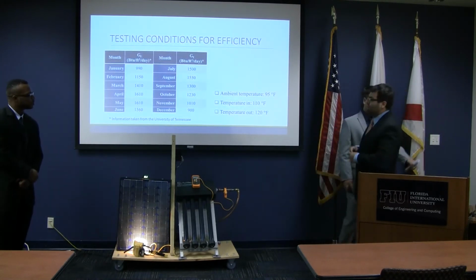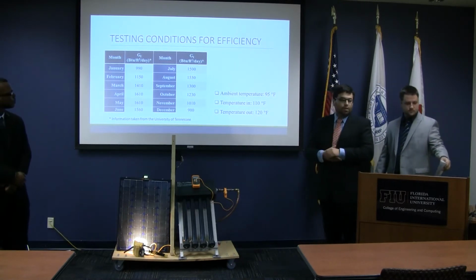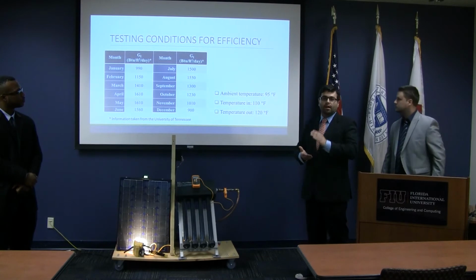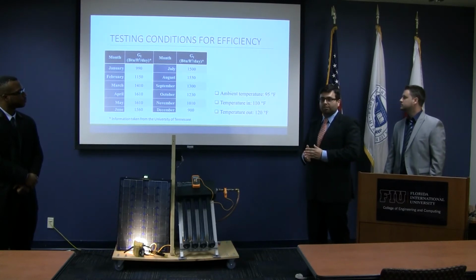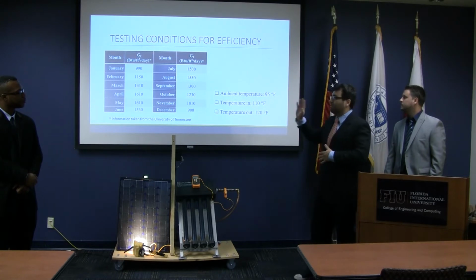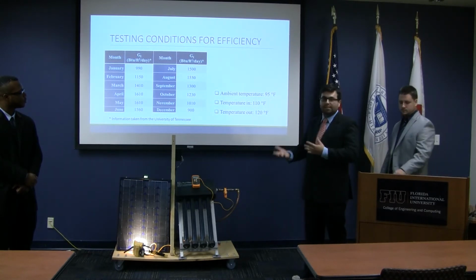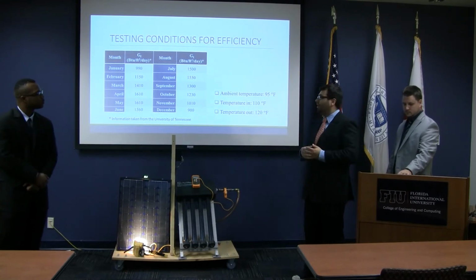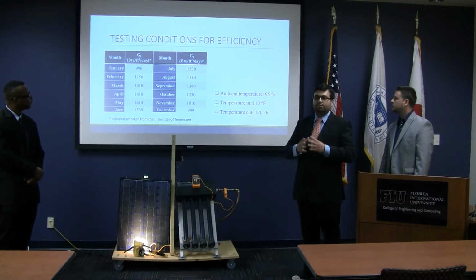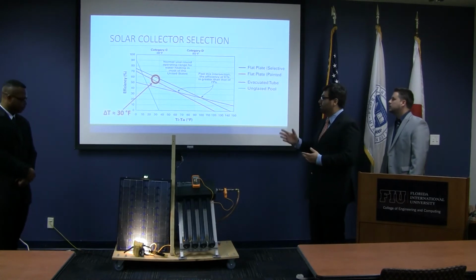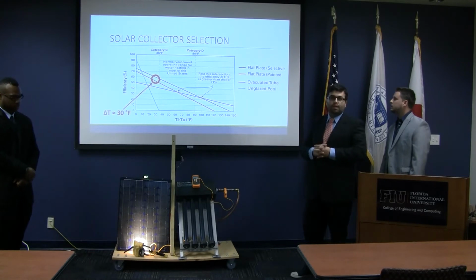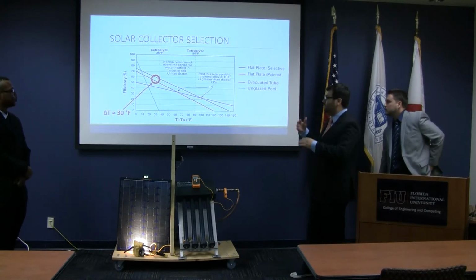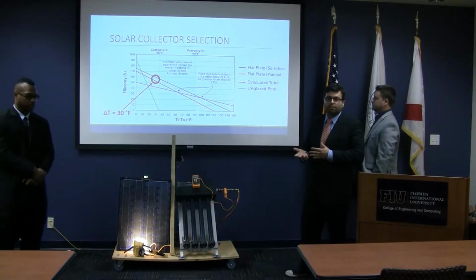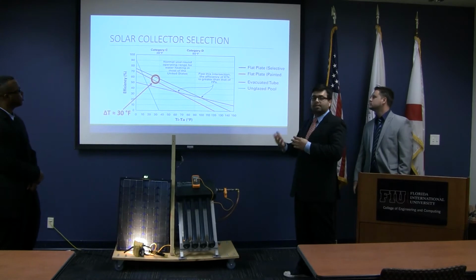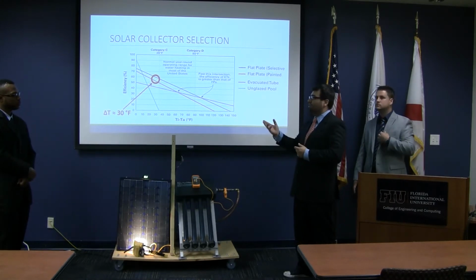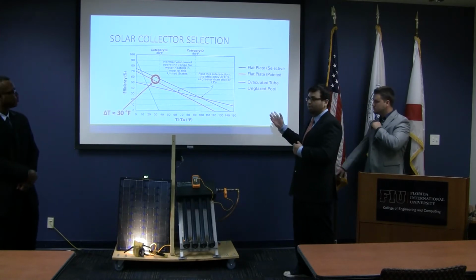So in terms of generating the heated water to power our chiller, we looked at different technologies that were available, and we selected that we were going to use solar collectors. And then we set up some conditions. We tested here in Miami, so we took the conditions here in Miami to determine what was the best kind of solar collector that was available for our project. Basically, there is the Solar Rating Corporation, which helped us determine. They test all the different solar collectors that are available, and they create efficiency equations that we use to determine what was the best fit to our design using the conditions that we have.